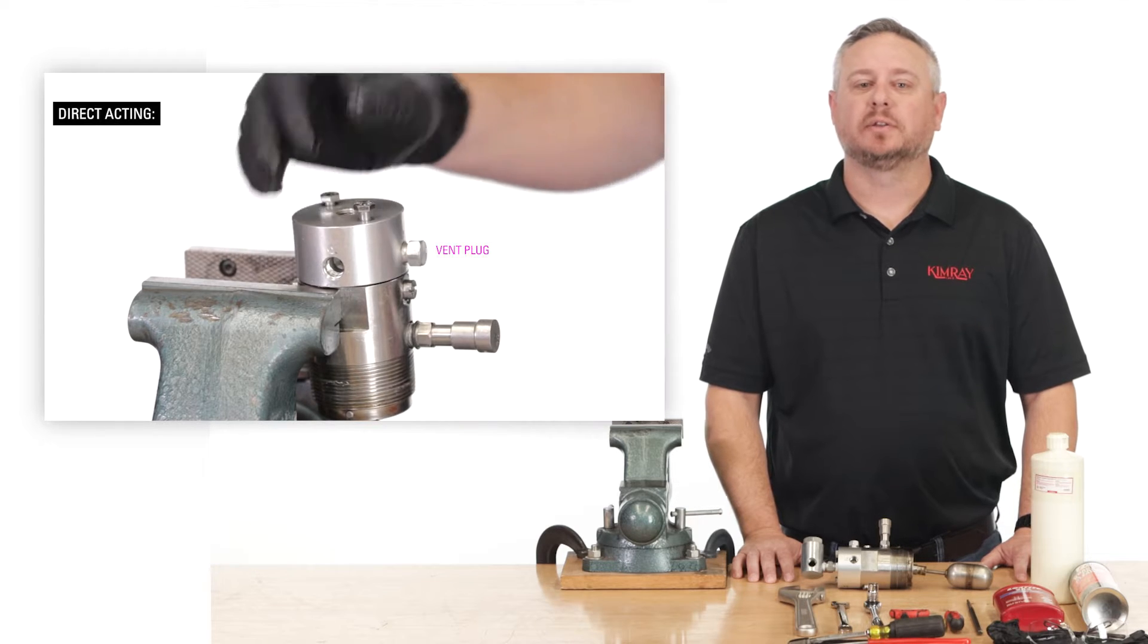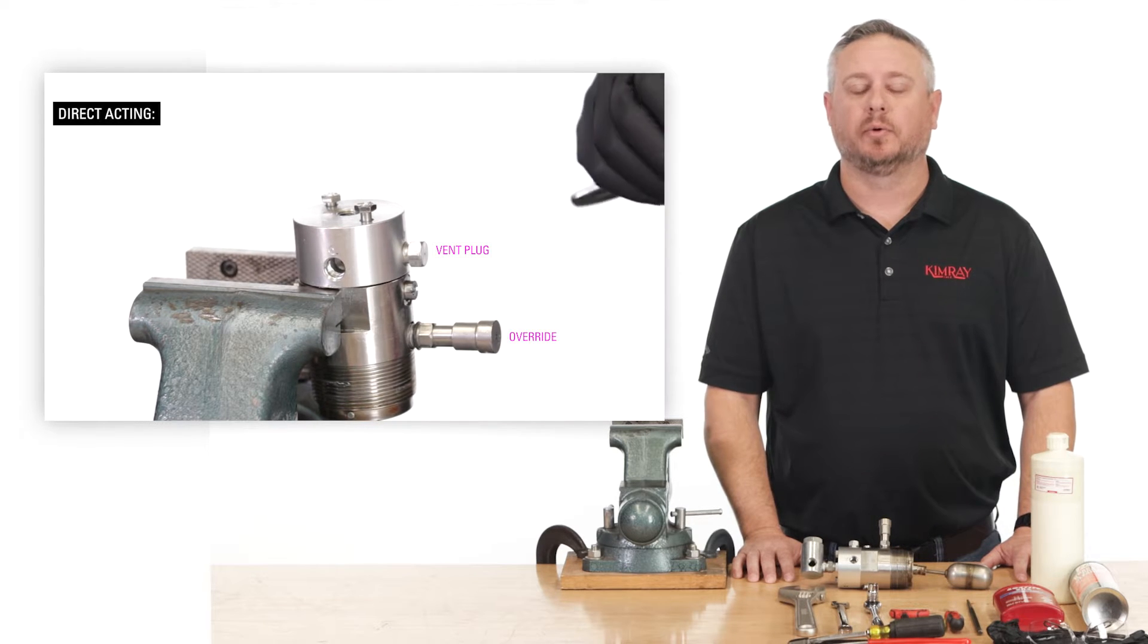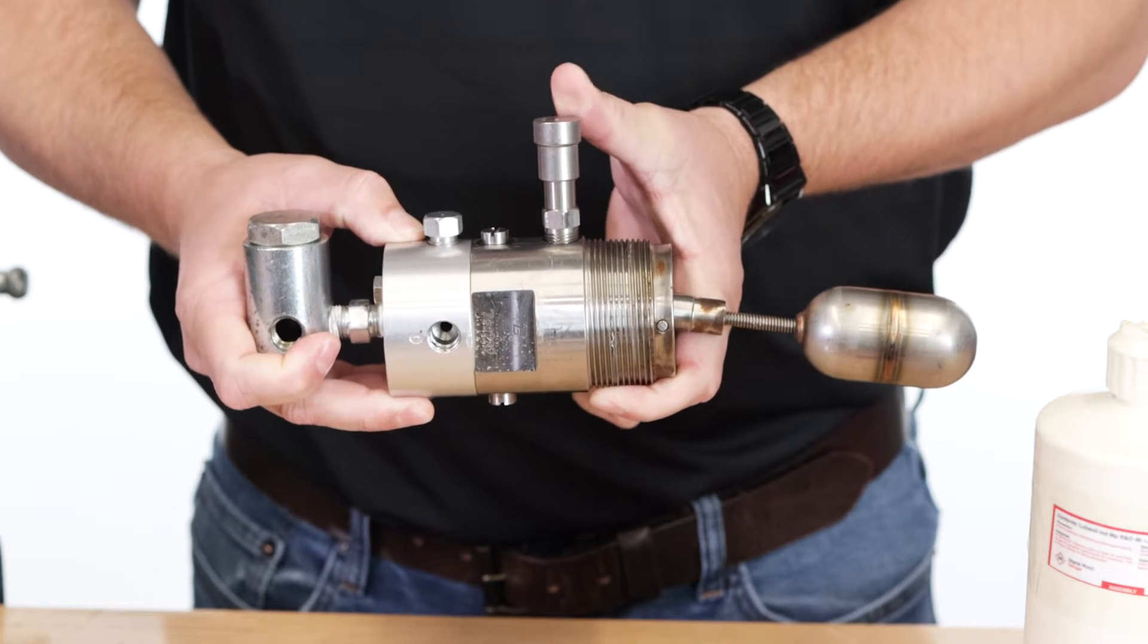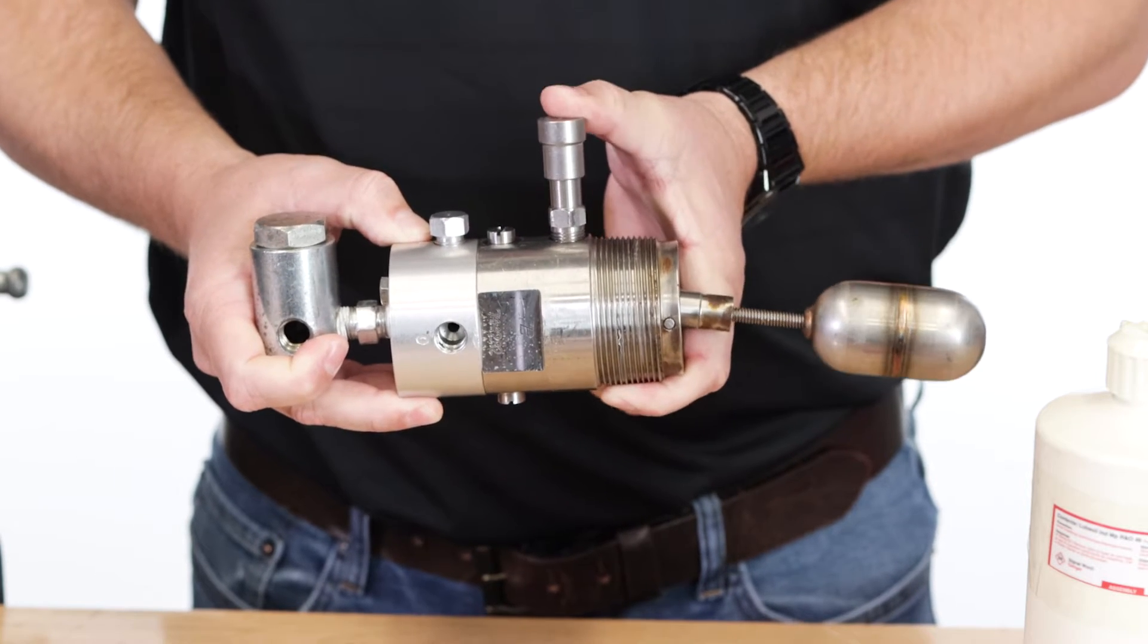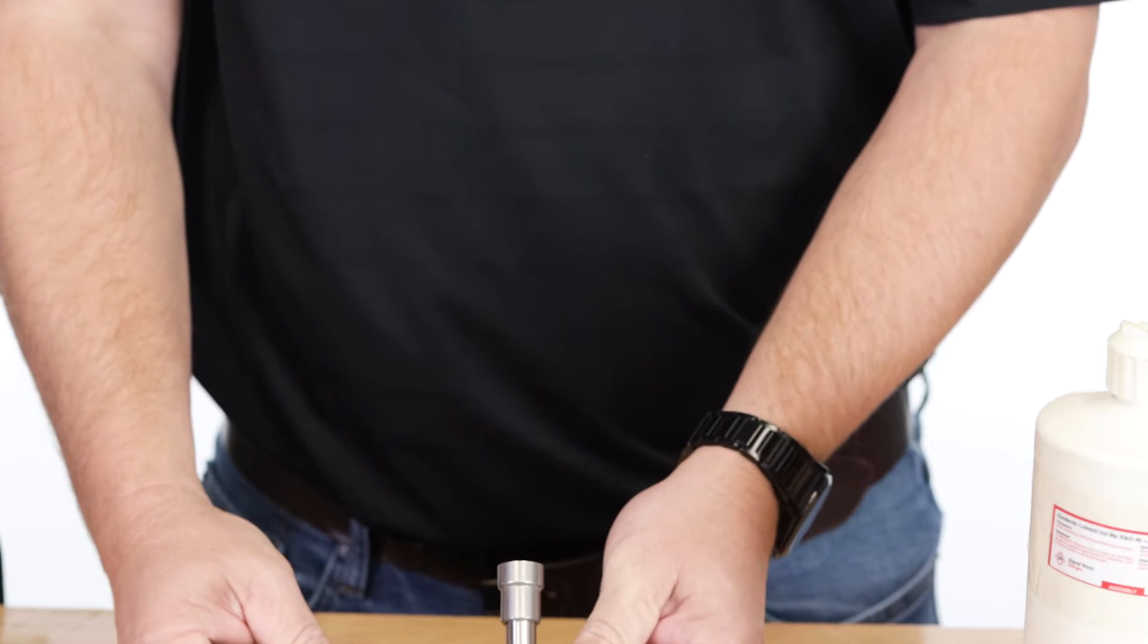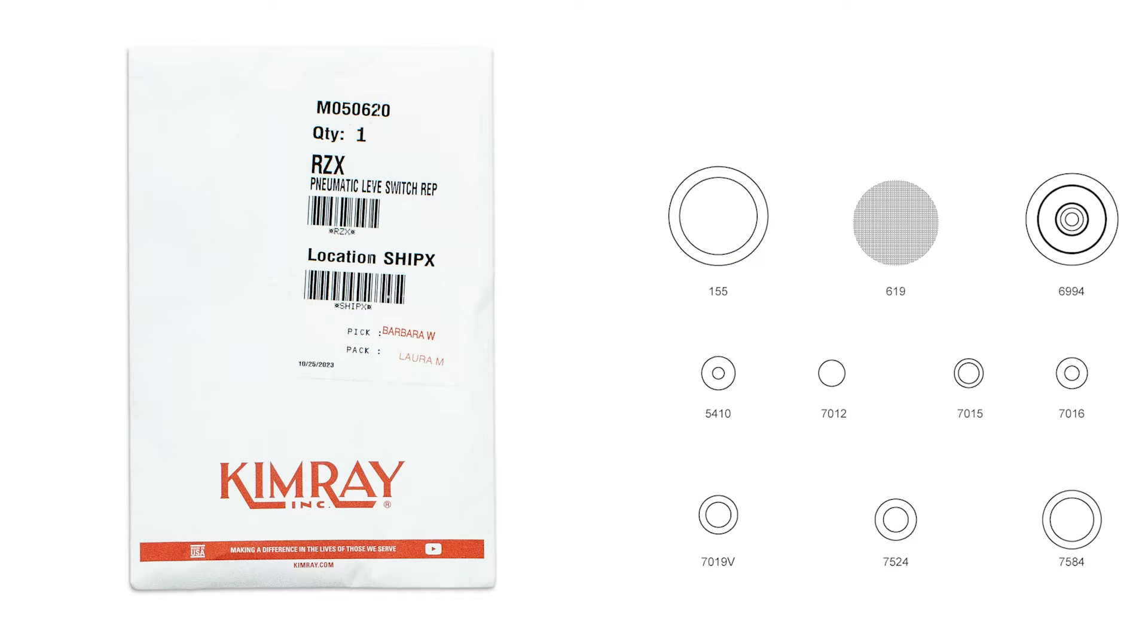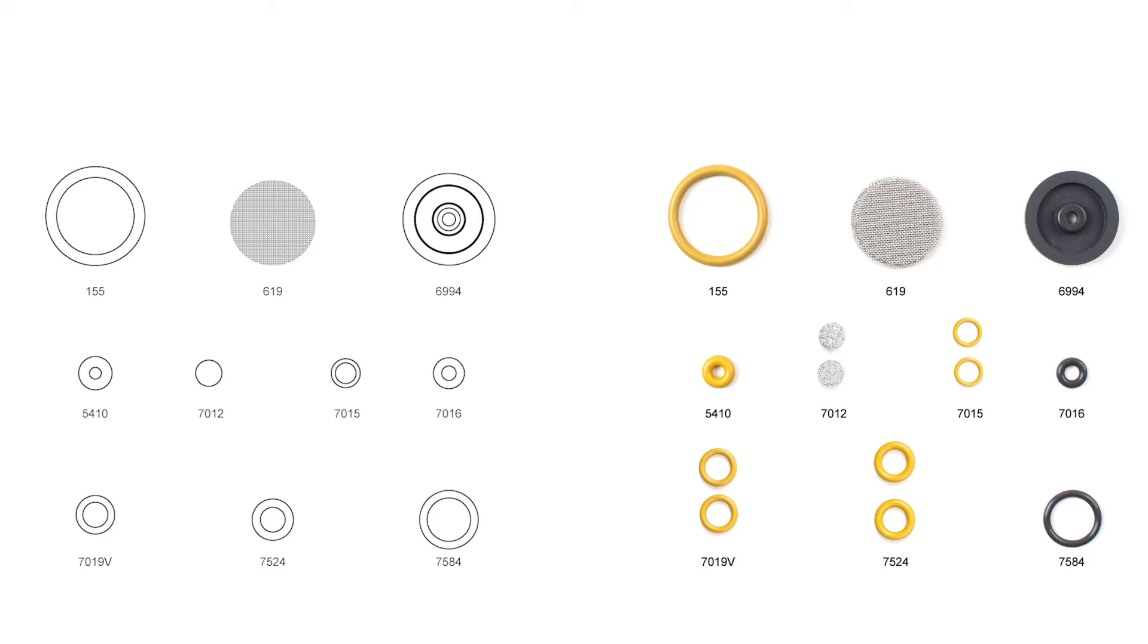We'll go over how to easily change this from direct to indirect later in the repair video. You can test the level switch by holding down the manual override. We recommend testing this at least every six months to confirm the level switch is working properly. We also recommend using a repair kit at least once a year for preventative maintenance. While the body will last for many years, the internal components and soft goods can wear out more quickly.